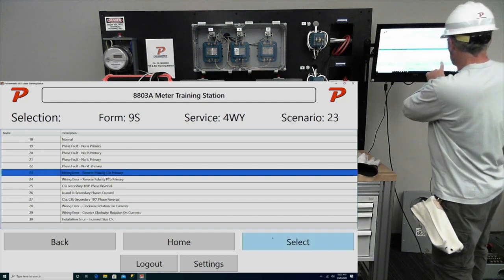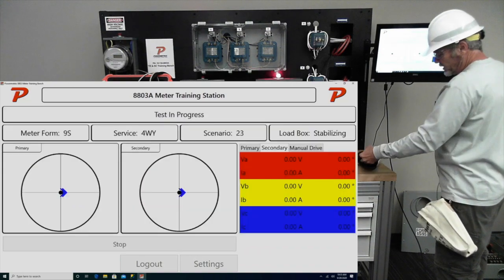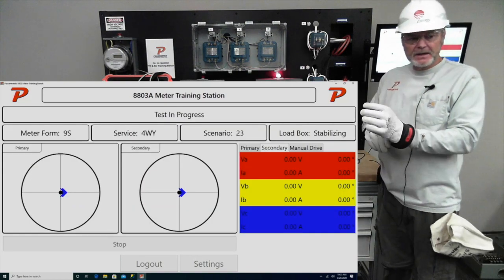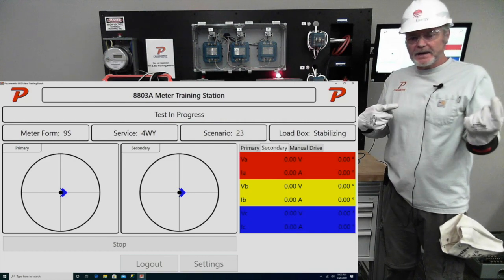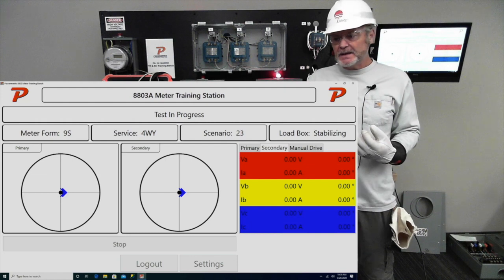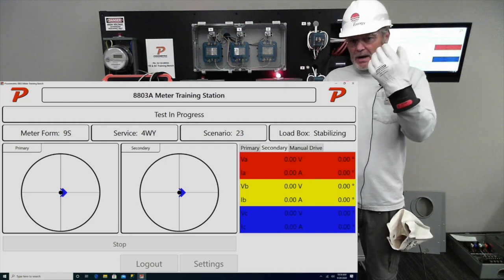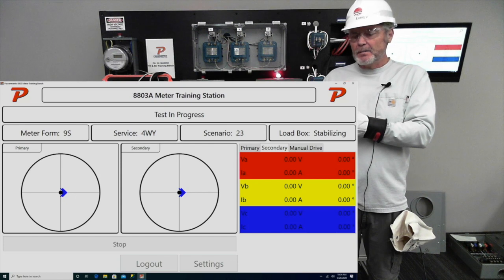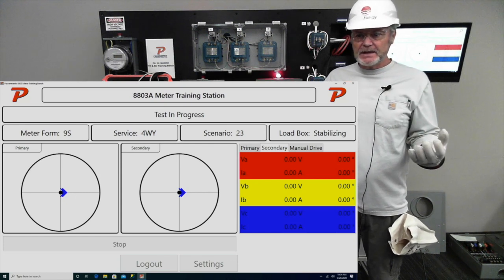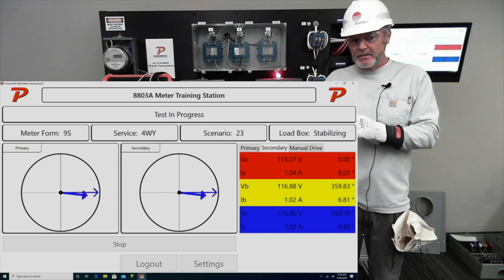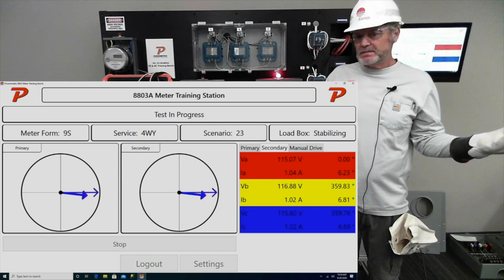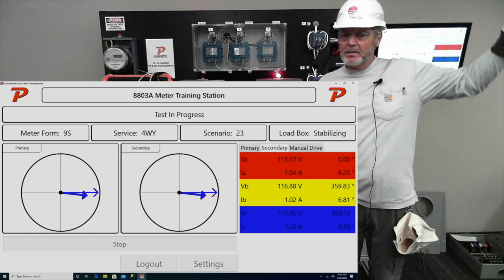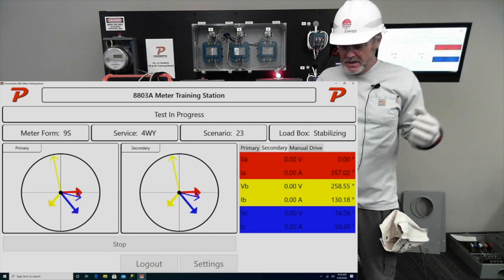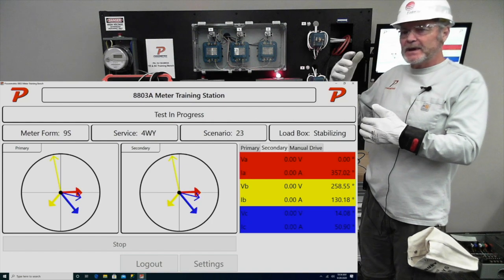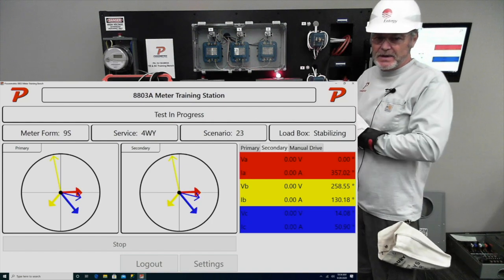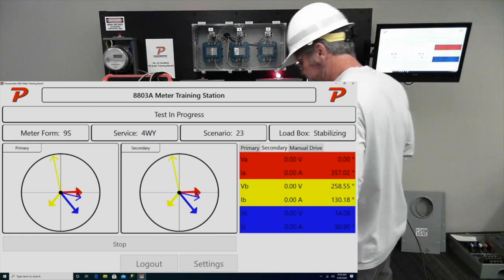The reason I want to is we can put problems on there, and we talk about this, using the machine to show you problems between primary and secondary. There's always that general rule that the secondary follows the primary. So if I have a problem on the primary, yeah, the secondary will follow that. But I need to know if I'm trying to troubleshoot the situation at that installation, is the problem on the primary side or the secondary side? Because it also decides what personnel have to be out there, right? Probably if it's primary stuff, I'm going to get some linemen out there. So it's definitely a big deal to decide whether it's a primary side issue or a secondary side issue for us as techs. So I've selected one.